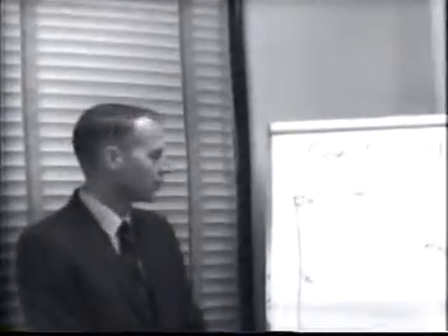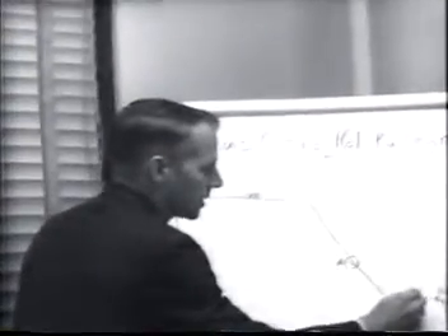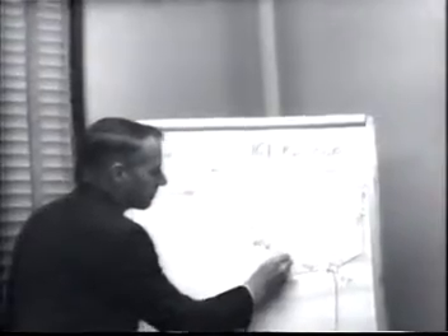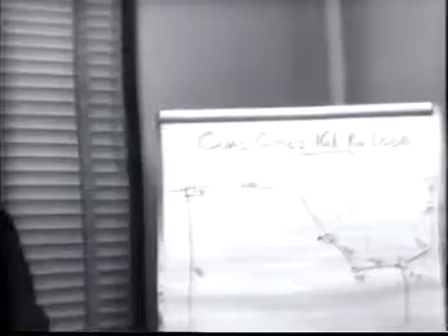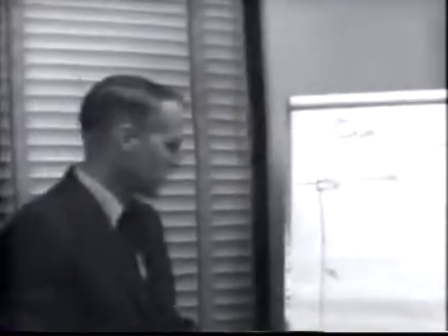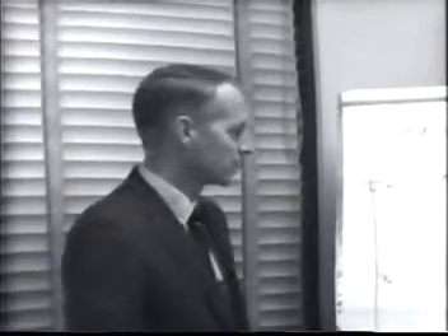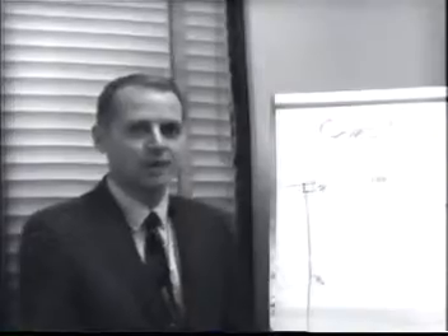But we can see here the pattern of expansion. It's very conceivable. These lines were built in 1968, incidentally. And this line in 1967. But we can see that the next stage of development of this system is the installation of substations at various points along these transmission lines and stepping down from 161,000 volts to 13,800 volts for use in serving the load in that particular area. We have a continual period of developing a loop system, breaking up the loops to serve individual substations, and then overlaying the given transmission system with one of a higher voltage.